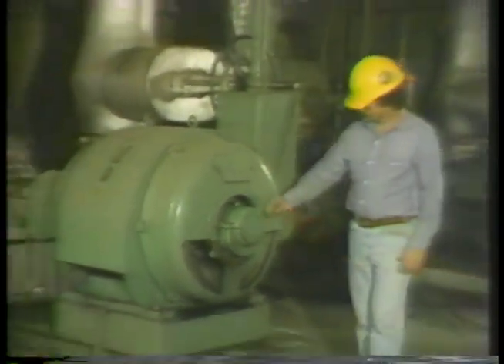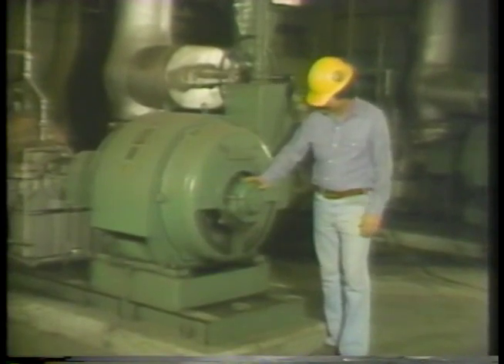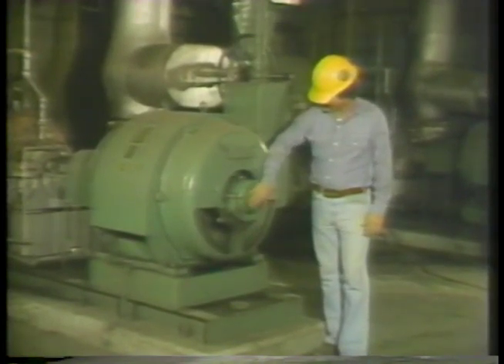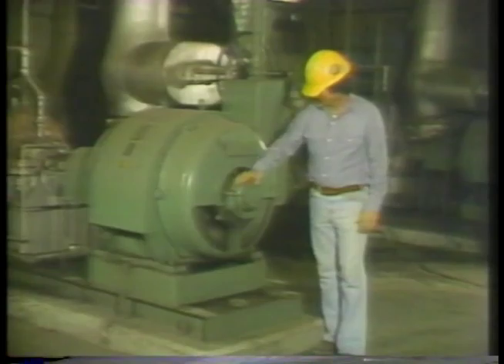If the temperature of an object is higher than our body temperature, we sense that it is hot. And we can become familiar with the temperature of an object to the point where we can tell if the temperature is about what it should be. For example, while making routine inspections in your plant, you will be able to touch the bearing housings of machinery and have a good idea if the bearing temperature is right.